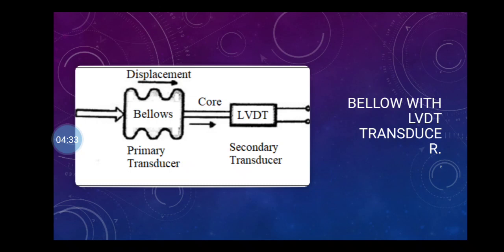On the non-magnetic bobbin, three coils are wound. First one is the primary coil of the transformer, which is excited by the AC supply. The secondary coil is divided equally and electrically connected in phase opposition, that is 180 degrees. When the primary is excited, voltages V1 and V2 are induced by mutual induction in the two sections of the secondary. When the magnetic core moves, then V1 is not equal to V2. So that's why an output voltage V1 minus V2, not equal to 0, appears on the secondary side, which is equal to the pressure measured by the gauge.